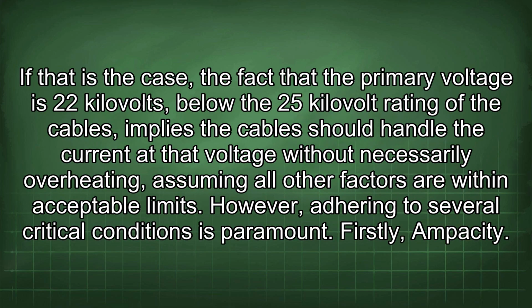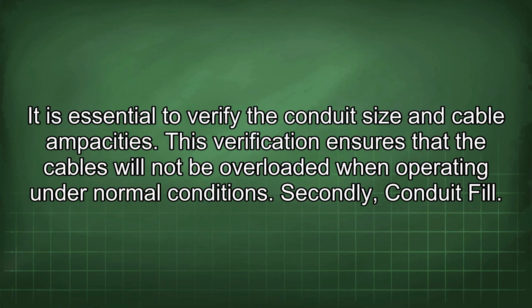If that is the case, the fact that the primary voltage is 22 kV, below the 25 kV rating of the cables, implies the cable should handle the current at that voltage without necessarily overheating, assuming all other factors are within acceptable limits. However, adhering to several critical conditions is paramount. Firstly, ampacity. It is essential to verify the conduit size and cable ampacities. This verification ensures that the cables will not be overloaded when operating under normal conditions.